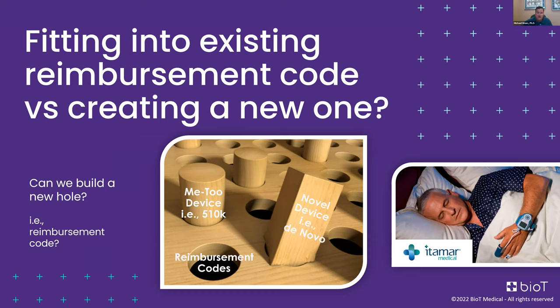On the other hand, if we're developing something new or novel, we're not going to bring it onto the market as a 510K, but rather as a de novo. The de novo is the alternative to the 510K for class two or lower devices. Unlike the 510K, a de novo does not require a predicate - you do not have to show your device is substantially equivalent to another device.